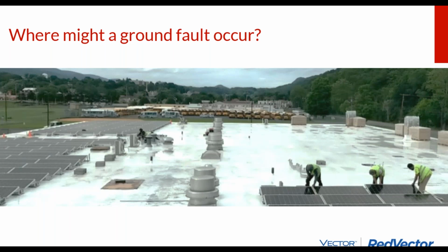So ground faults are much more dangerous. An arc fault could find a path to ground and then become a ground fault quite easily. And so this is a rooftop we did in West Virginia, and as you can tell, the roof fills up with water every single time it rains. The roof elevation was not such that when they installed the drains on the roof, they could put the drains below the roof deck. Instead, in order to adequately seal the penetrations made by the drains, the drain holes all had little levees built up around them. And so, in fact, the rooftop needed to hold about 2 or 3 inches of water before any of the water made it into the drains.